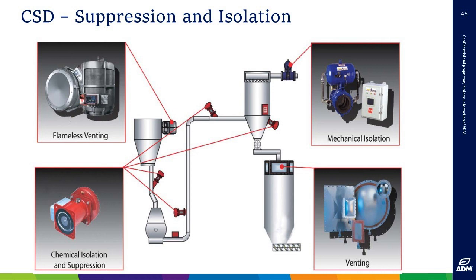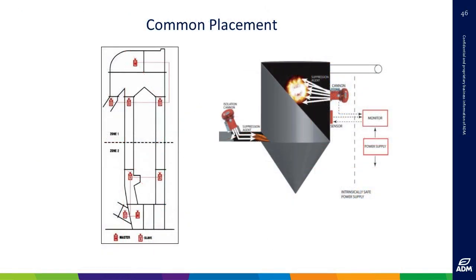Where do you place them? Common spots. I'm assuming nobody here designs their own suppression systems, but if you do, or have somebody do it, don't just accept them putting it wherever. Go back to the documentation, have that design document in hand, the drawing showing where they're supposed to be placed, how many feet from the bonnet on the discharge can that bottle be, whatever it is. Keep it, don't lose it, don't throw it in the banker's box in the basement where the river floods and washes it all away so you never have it again.